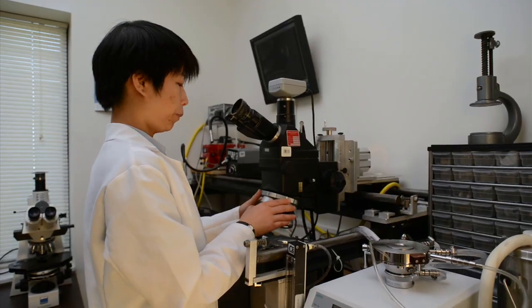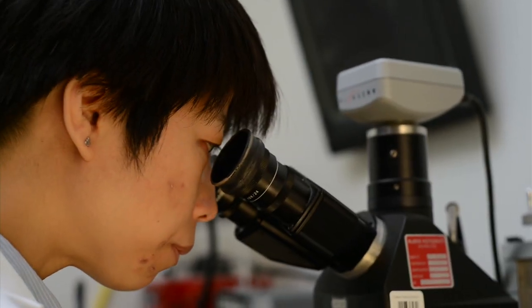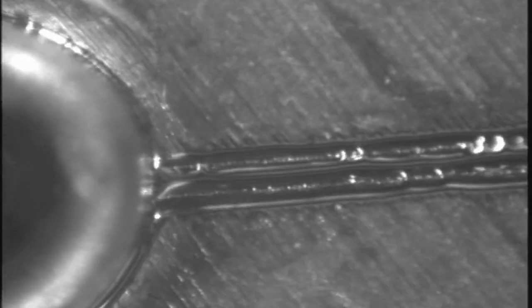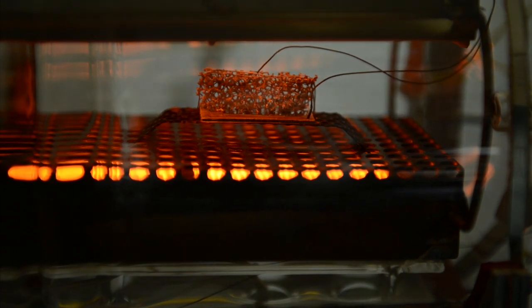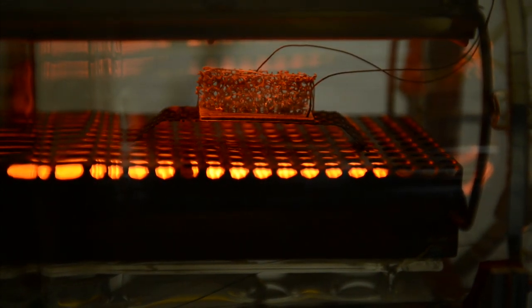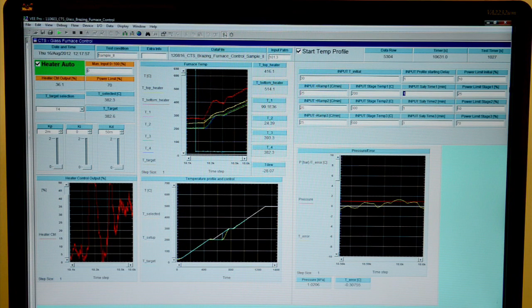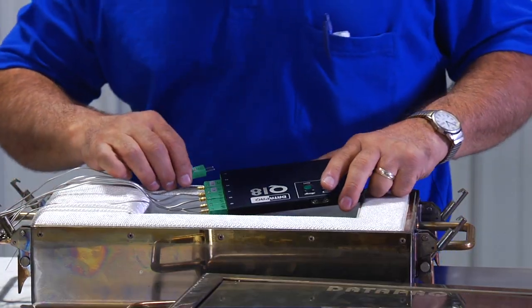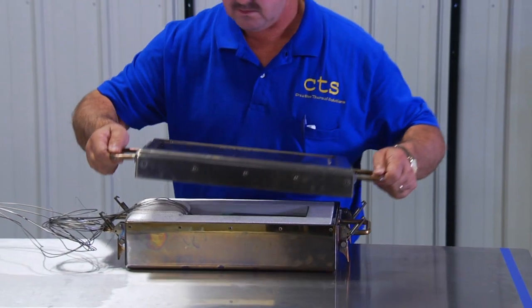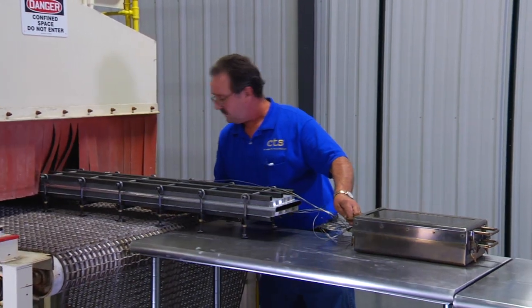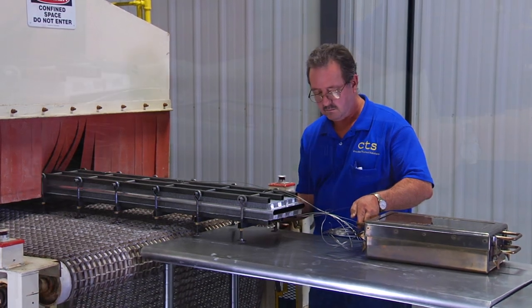My name is Hui Zhao. I work here as a senior research engineer at Creative Thermal Solutions. So my job activities are mainly related to aluminum brazing and brazing of other advanced materials. Here in this brazing lab, we use the transparent glass furnace to visualize the brazing process, and therefore we can learn how the brazing conditions such as the heating ramp, peak brazing temperature, background atmosphere, as well as the material selections can influence the final quality of the products. And then we can transfer this knowledge into the manufacturing process using our continuous brazing line. And we also have the state-of-the-art measurement technology for the temperature profile inside the furnace, which is really a Datapaq system that can track the temperature of the brazed parts when they are going through the heating zone of the continuous furnace.